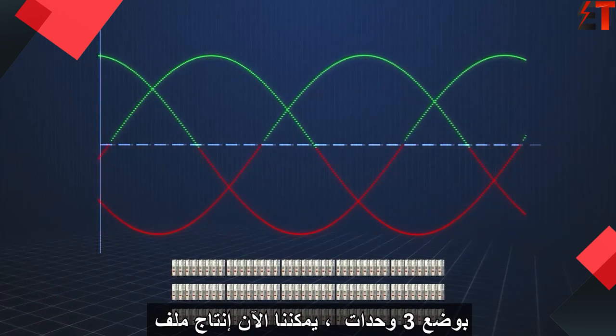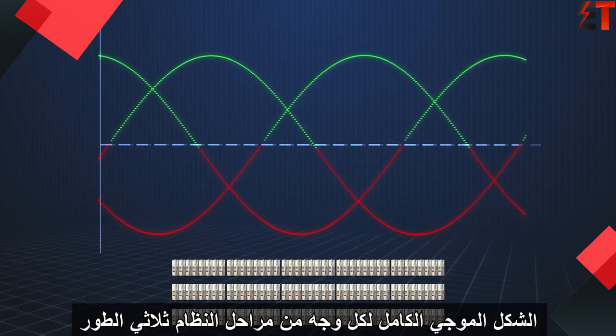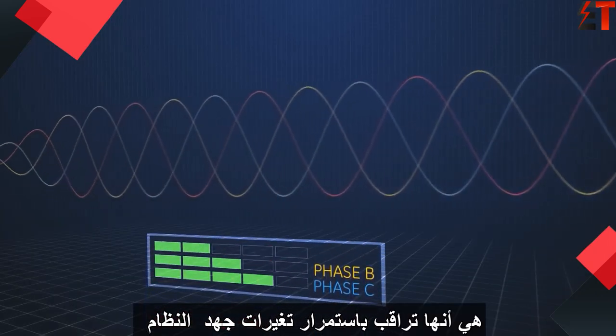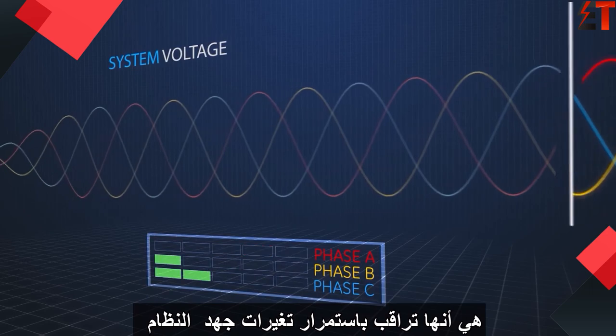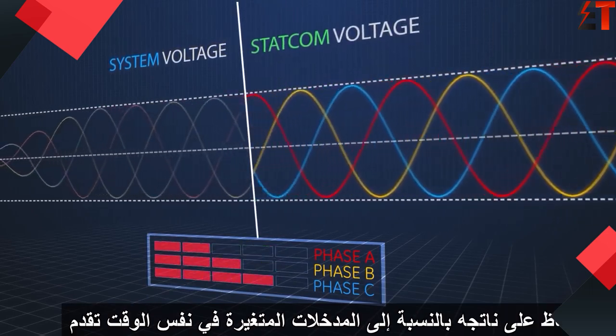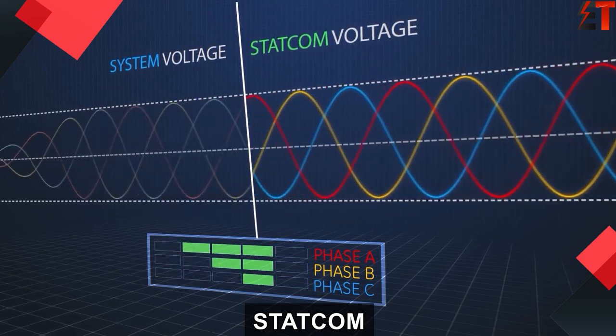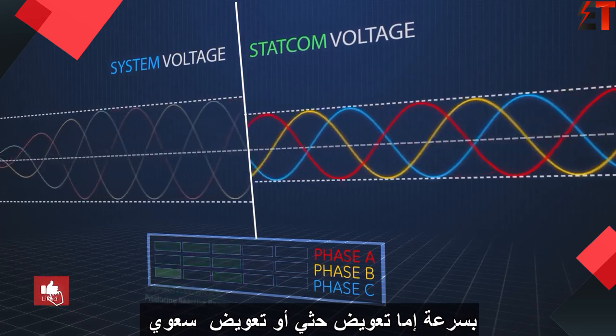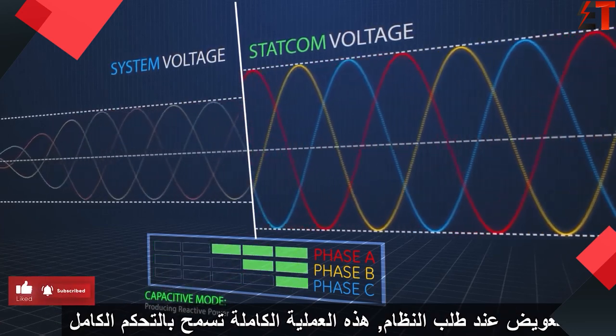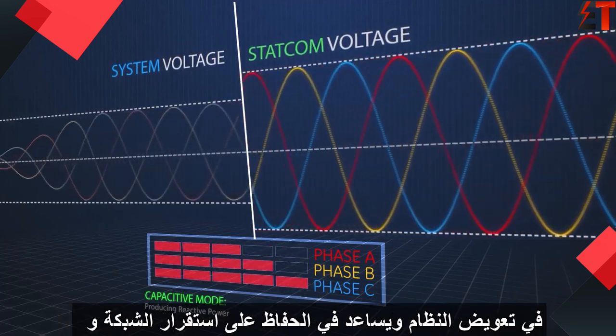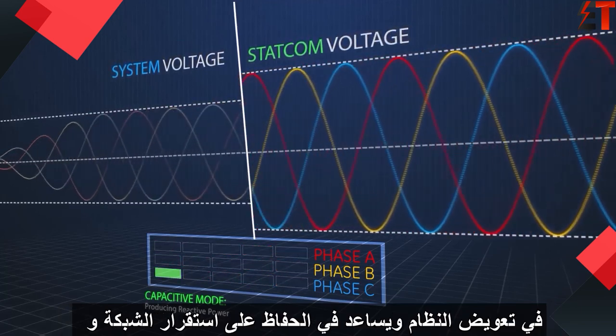Stacking the modules three high, we can now produce a complete waveform for each phase of the three-phase system. The sophistication of the STATCOM is that it continually monitors the always-changing system voltage to maintain its output relative to the changing input. Simultaneously, the STATCOM rapidly provides either inductive or capacitive compensation when required, allowing total control over system compensation and helping to maintain grid stability and boost efficiency.